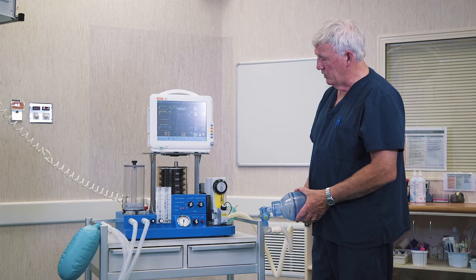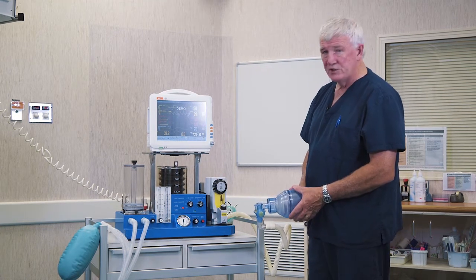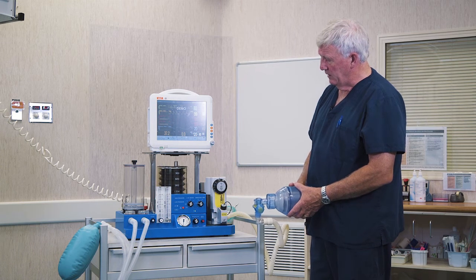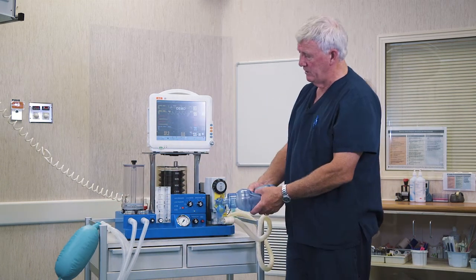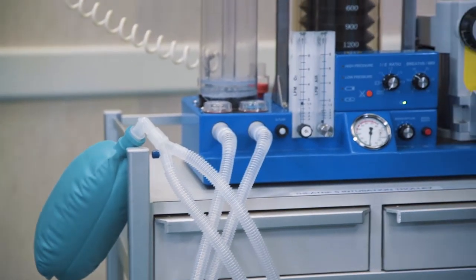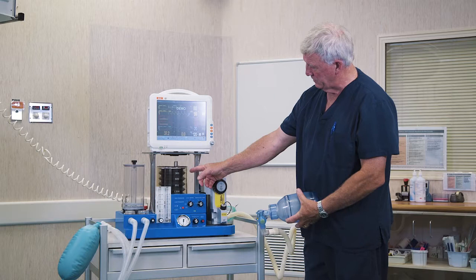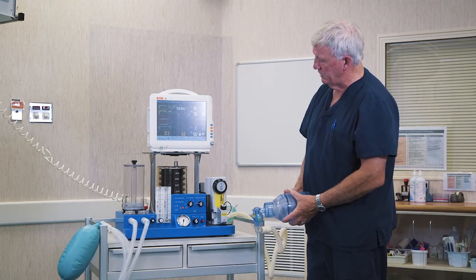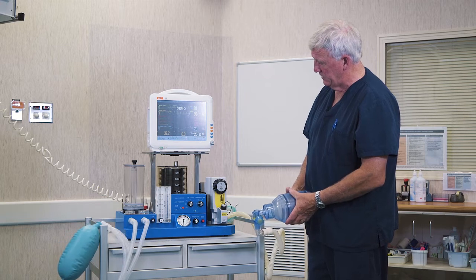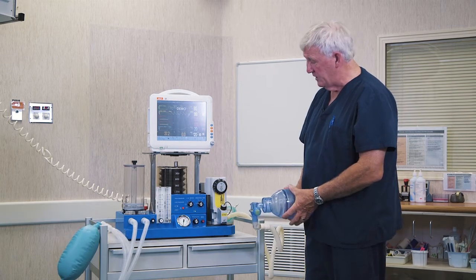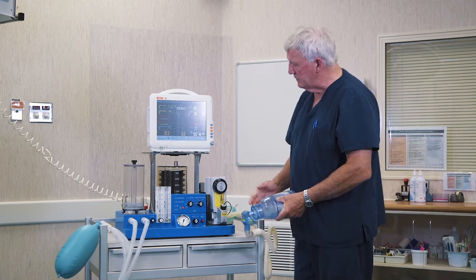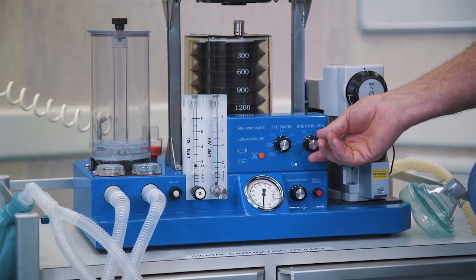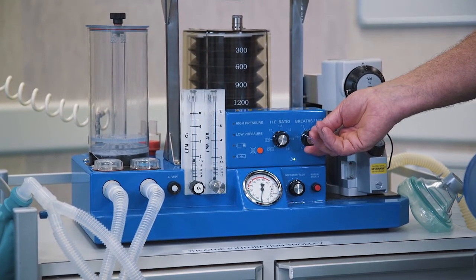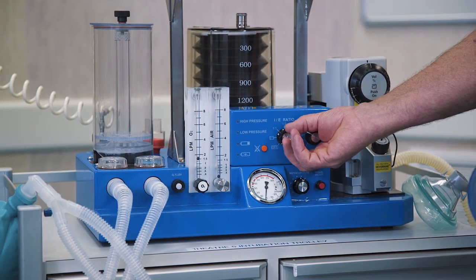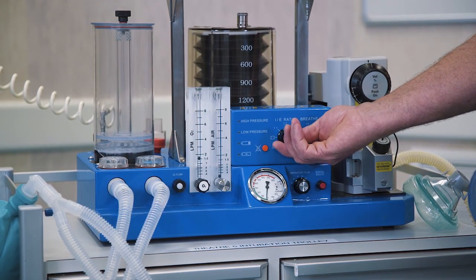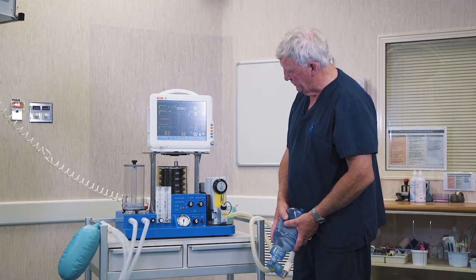Ivan's covered the workings of the machine, and I just wanted to go over it from the anaesthetic perspective, from the user's point of view. Now, this is the patient's lungs, and I'm ventilating with this bag. This is a self-inflating bag, and you can see the lungs going up and down, and of course the bellows going up and down. So the patient can either be breathing spontaneously, or I can take over and ventilate the patient. Now, if we want to change the patient to the ventilator, it's quite simple. We don't have to change any switches at all. All we do is turn the respiratory rate to what we want, say 12 breaths per minute. With this knob here, we put the IE ratio up to 1 to 2, and it'll automatically start ventilating. It cuts this bag out automatically, so we're on ventilatory mode there.